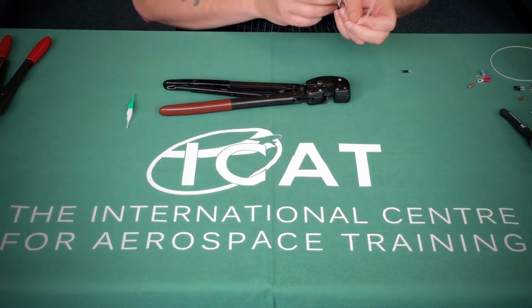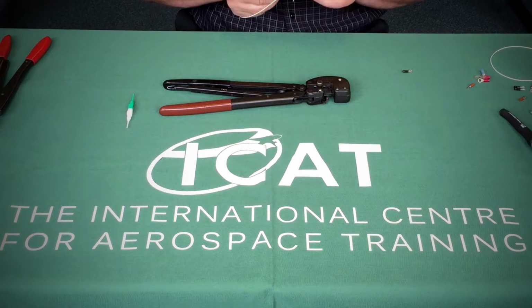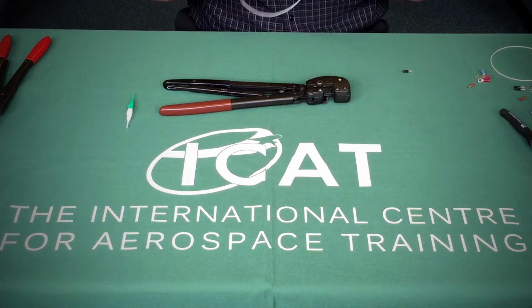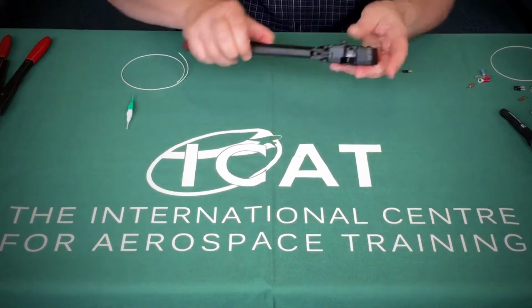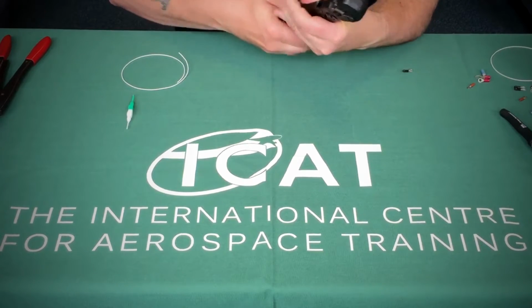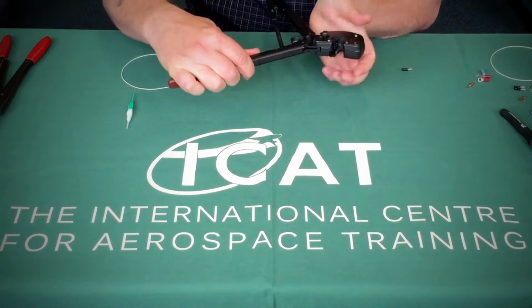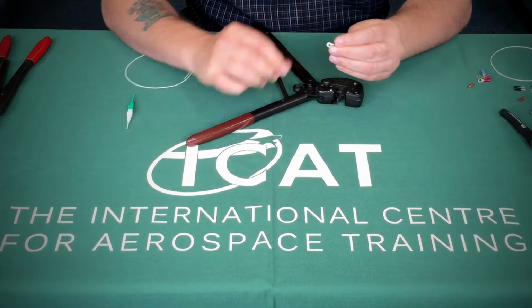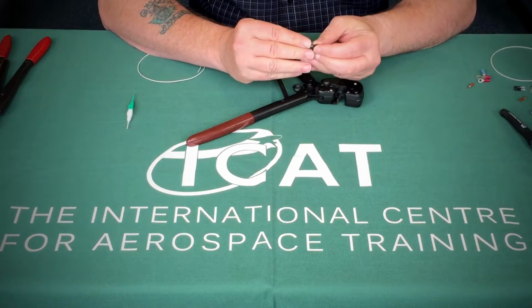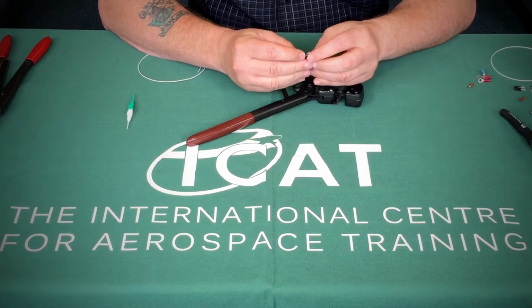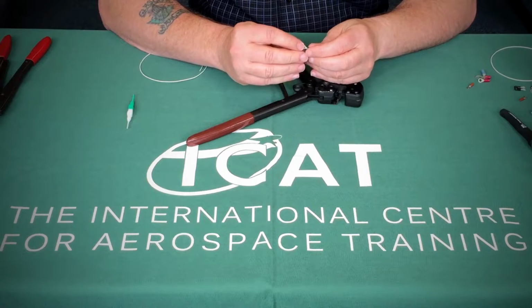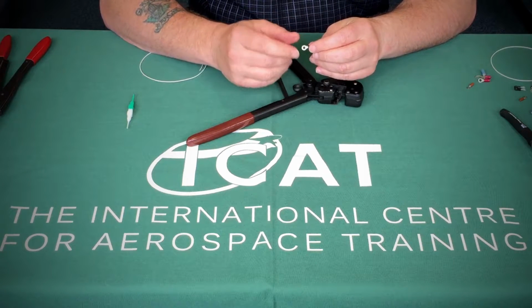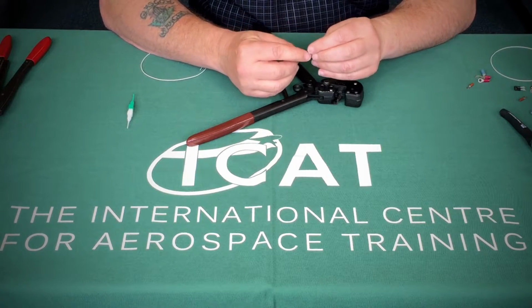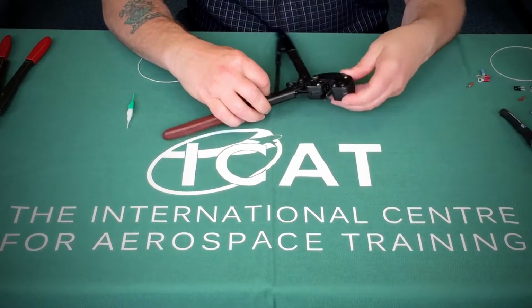With an insulated piece of cable, we can now attempt to ensure that the crimp is supported by the insulation and not just by the conductor itself. If it was only supported by the conductor itself, there is a chance that any vibration, wear or tear could damage the conductor and it may become more brittle and the crimp would not be secure.